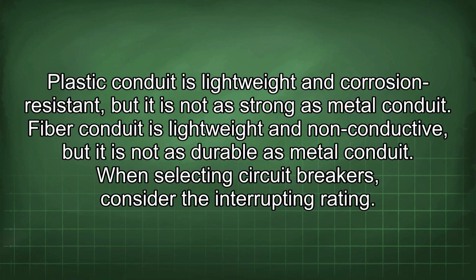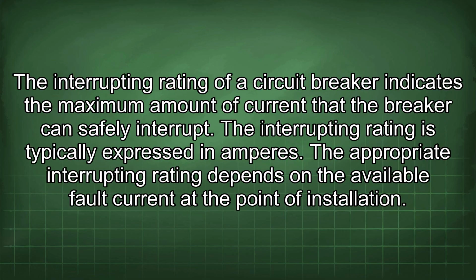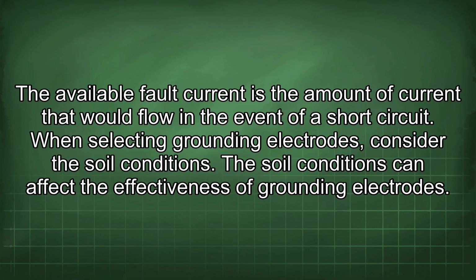When selecting circuit breakers, consider the interrupting rating. The interrupting rating of a circuit breaker indicates the maximum amount of current that the breaker can safely interrupt. The interrupting rating is typically expressed in amperes. The appropriate interrupting rating depends on the available fault current at the point of installation. The available fault current is the amount of current that would flow in the event of a short circuit.